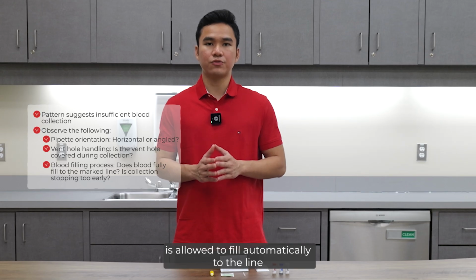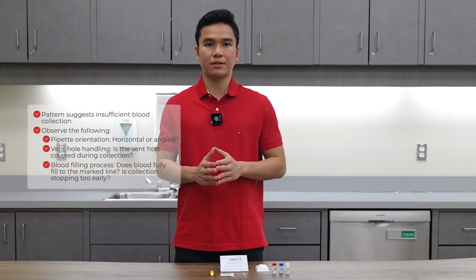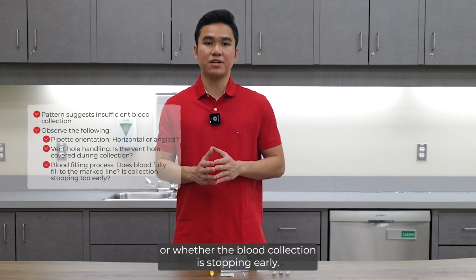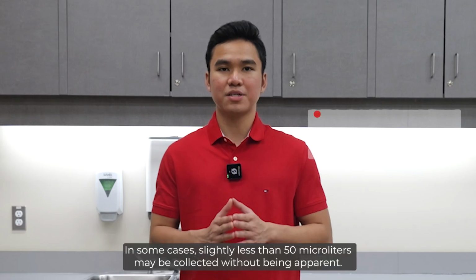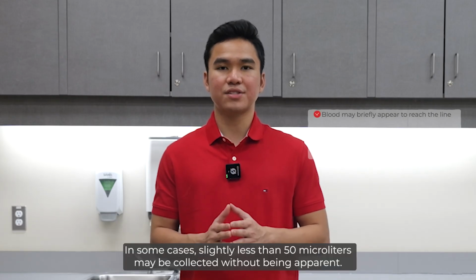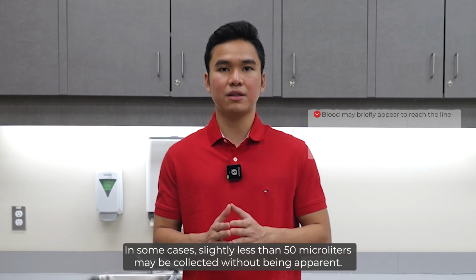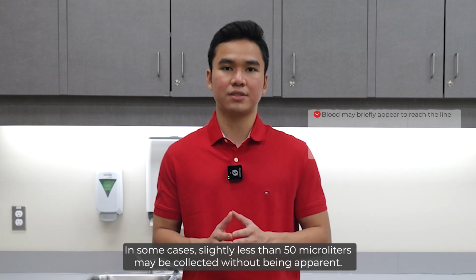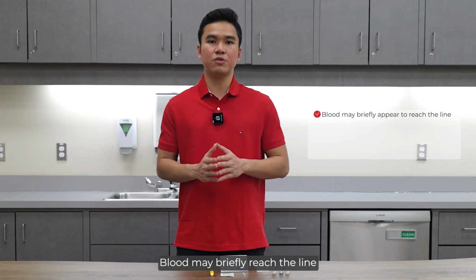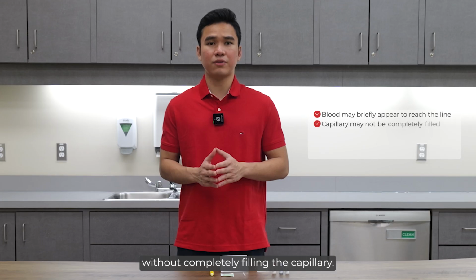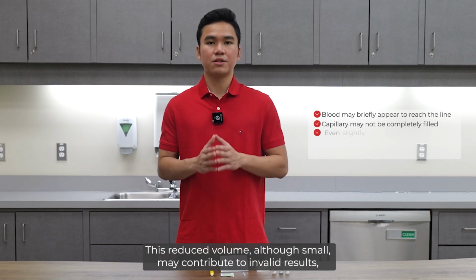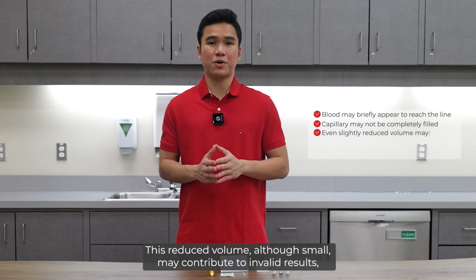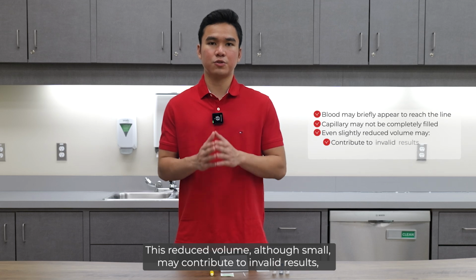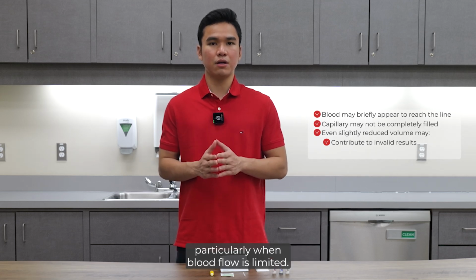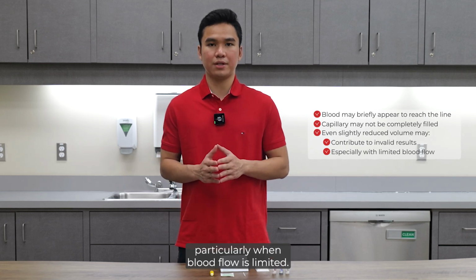Finally, check whether the blood is allowed to fill automatically to the line or whether the blood collection is stopping early. In some cases, slightly less than 50 microliters may be collected without being apparent. Blood may briefly reach the line without completely filling the capillary. This reduced volume, although small, may contribute to invalid results, particularly when blood flow is limited.